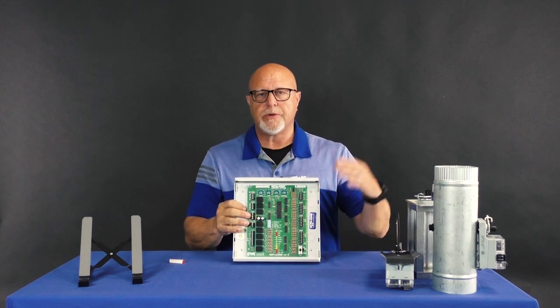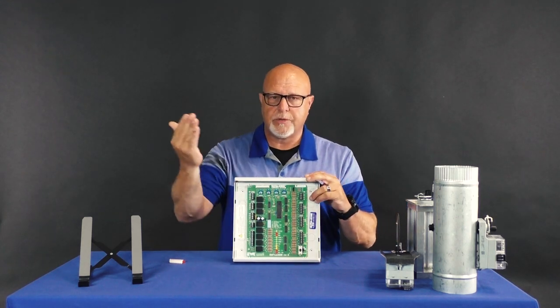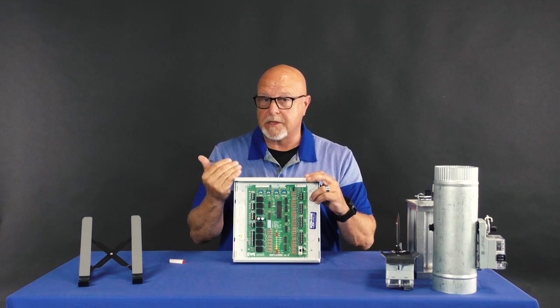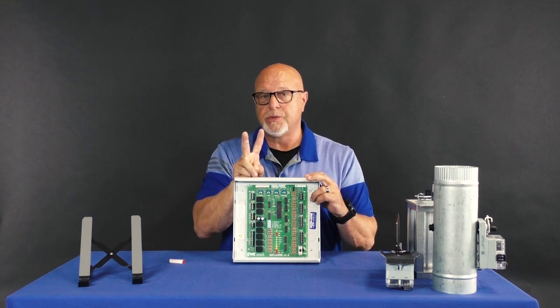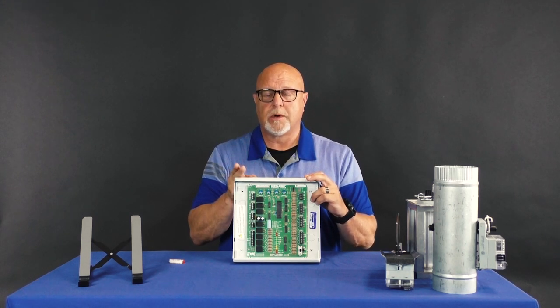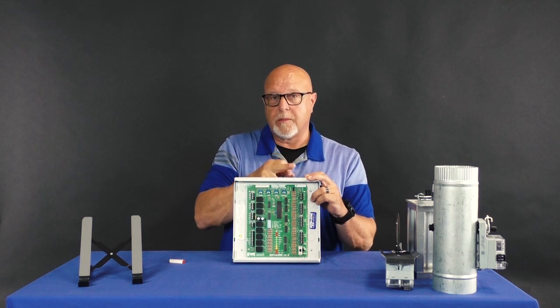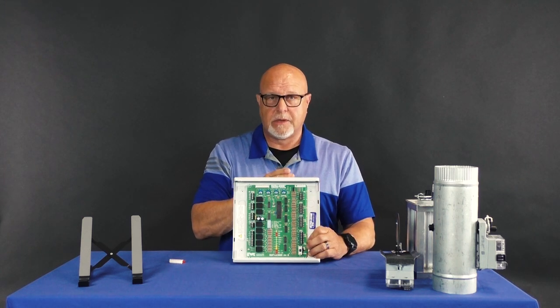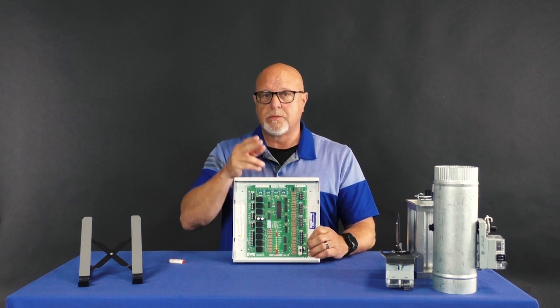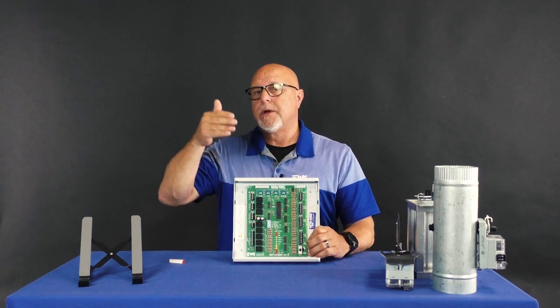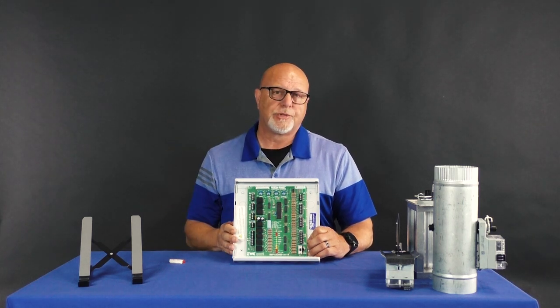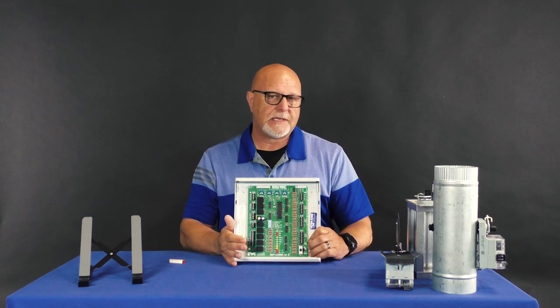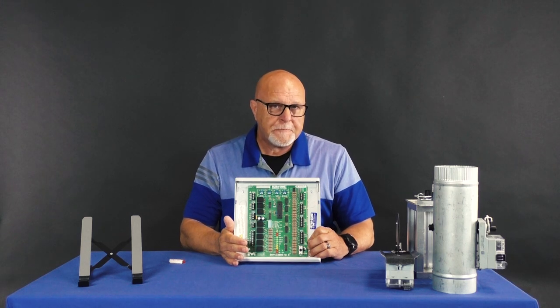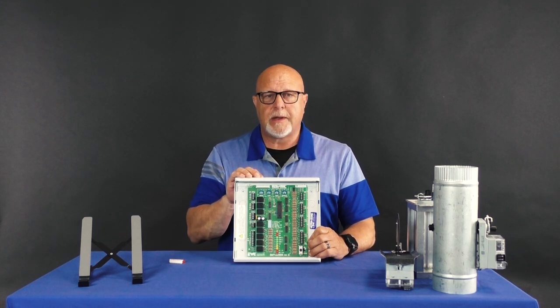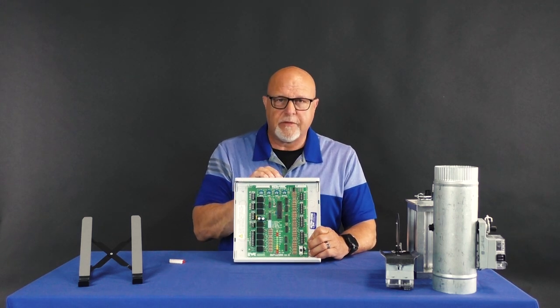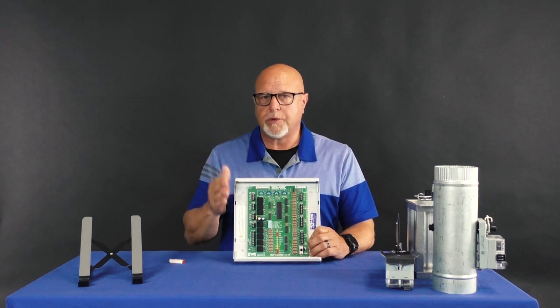You would then bring your new dampers to the panel. You would bring your new thermostat or thermostats to the panel because it is a 2-zone add-a-zone board. We can go from a BM Plus 3000 in 2 zones at a time to a maximum of 7 zones, just as if you had bought the BM Plus 7000 originally. So this enables you to put add-a-zones in after the fact without buying a whole new panel.